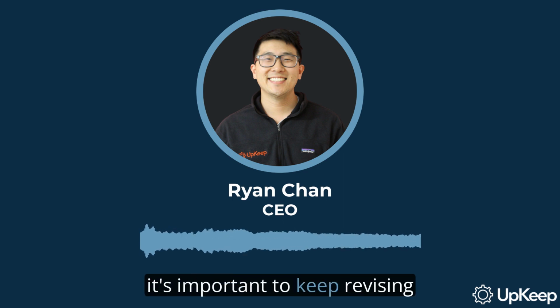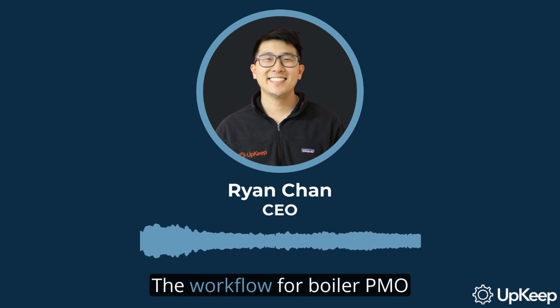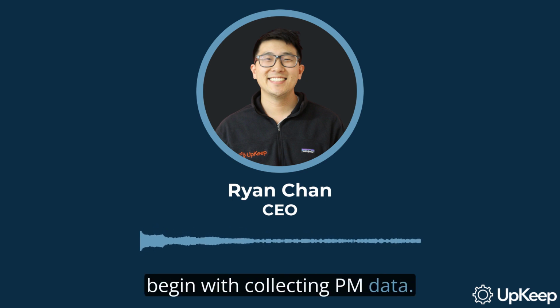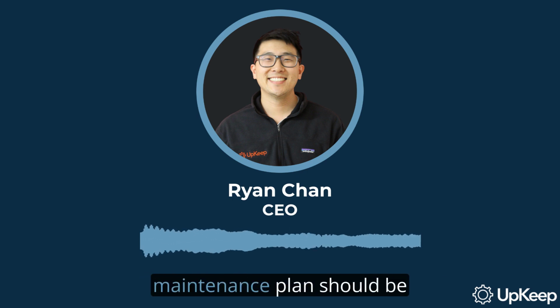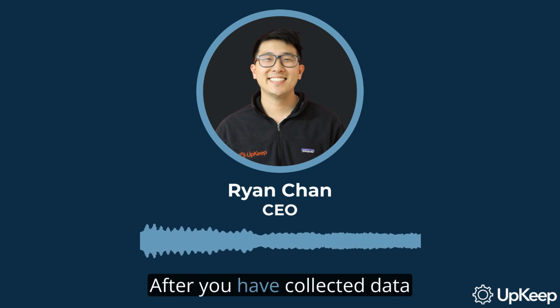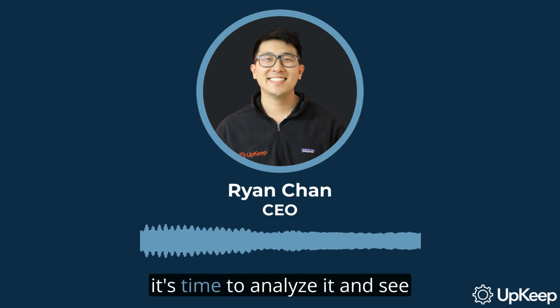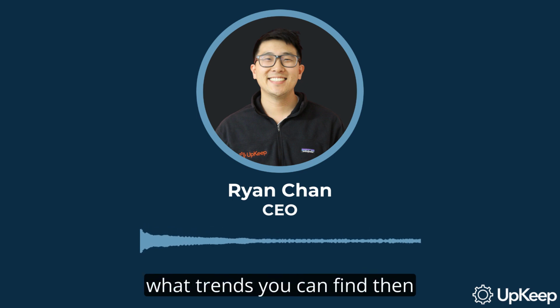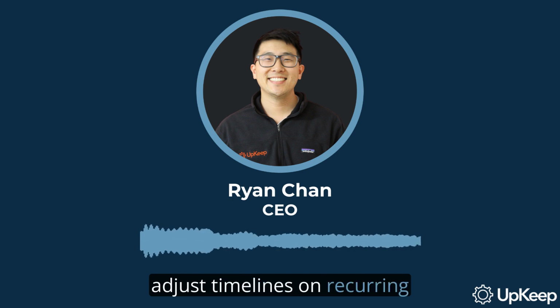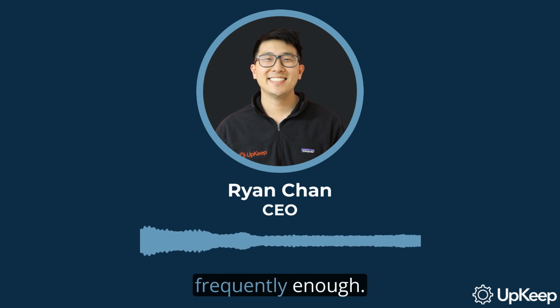Now, if you already have a boiler preventive maintenance plan in place, it's important to keep revising it to make it as lean as possible. Each planned task should be effective so as to avoid wasting time and resources. The workflow for boiler PMO often includes the following elements. Begin with collecting PM data. Any decisions you make about your boiler's preventive maintenance plan should be grounded in actual data. Next, analyze the data. After you have collected data on your boilers for a while, it's time to analyze it and see what trends you can find. Then, adjust timelines on recurring tasks if needed. Some PMs may be performed too frequently, while others aren't performed frequently enough.